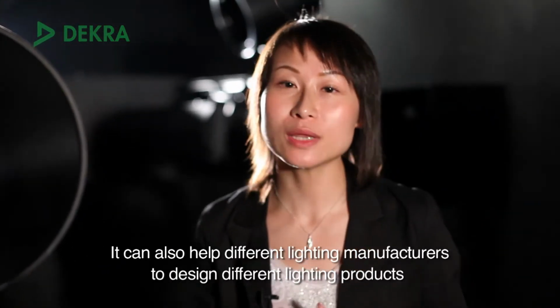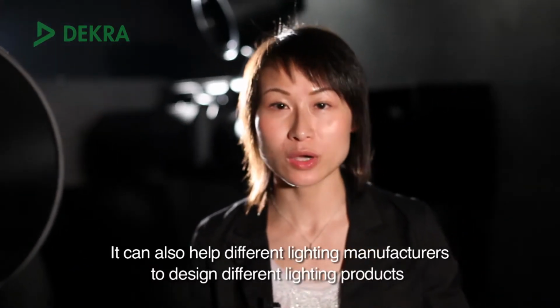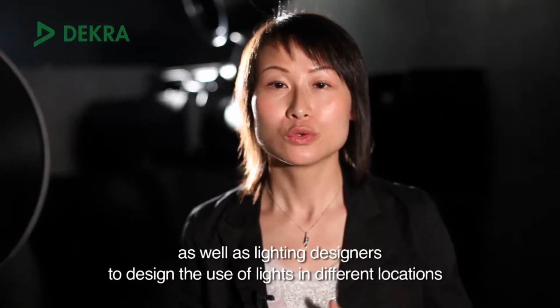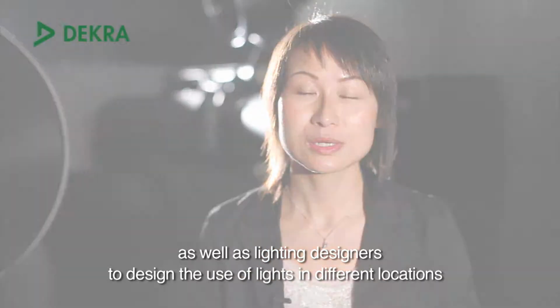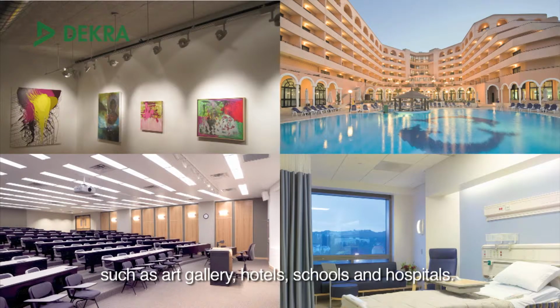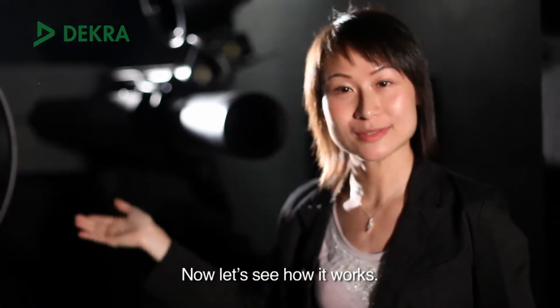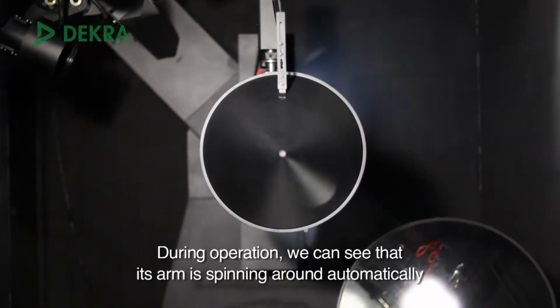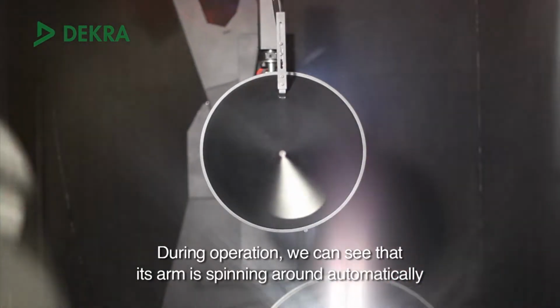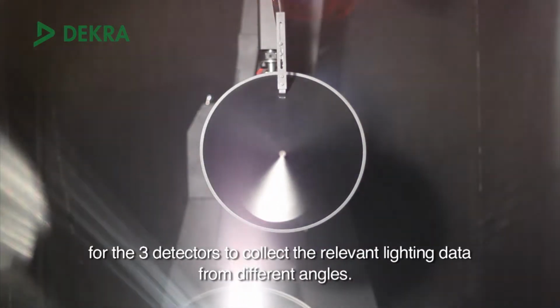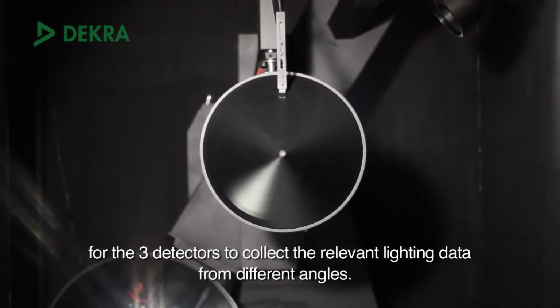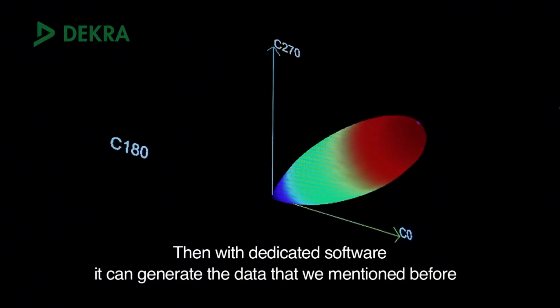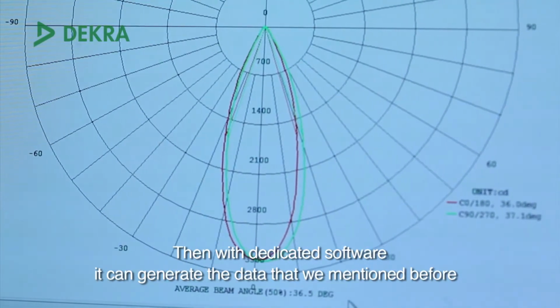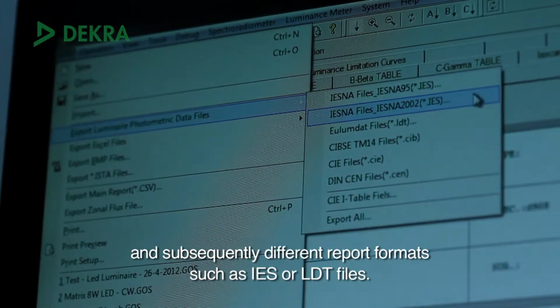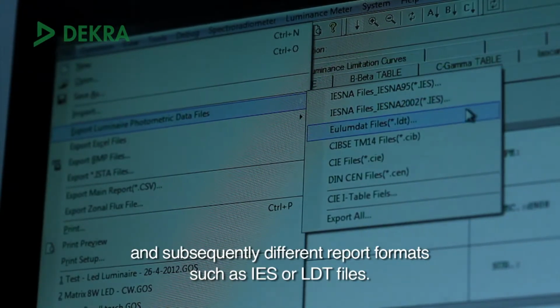It can also help different lighting manufacturers to design different lighting products, as well as lighting designers to design the use of lights in different locations such as art gallery, hotels, schools, and hospitals. So now let's see how it works. During operation, we can see that its arm is spinning around automatically for the 3 detectors to collect the relevant lighting data from different angles. Then with dedicated software, it can generate the data that we mentioned before and subsequently different report formats such as IES or LDT files.